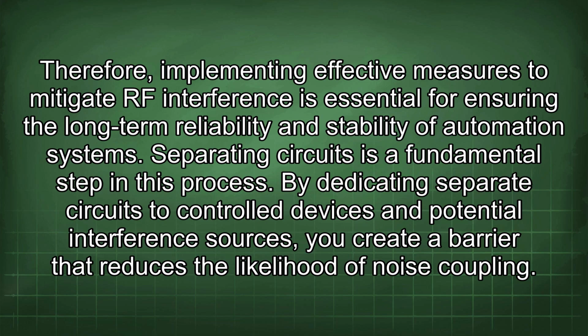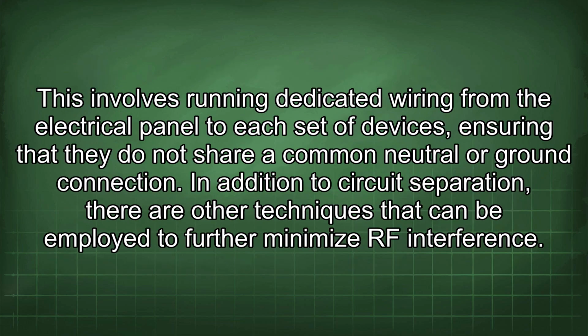Separating circuits is a fundamental step in this process. By dedicating separate circuits to controlled devices and potential interference sources, you create a barrier that reduces the likelihood of noise coupling. This involves running dedicated wiring from the electrical panel to each set of devices, ensuring that they do not share a common neutral or ground connection.